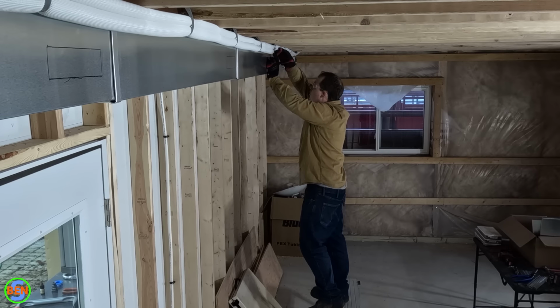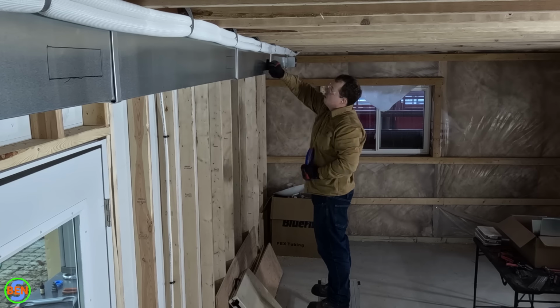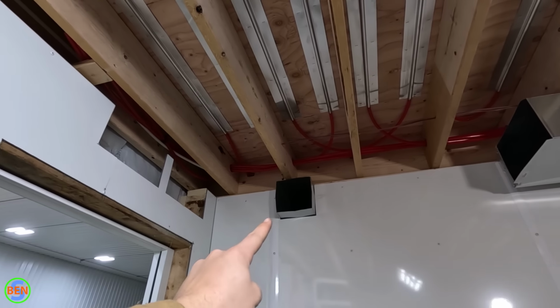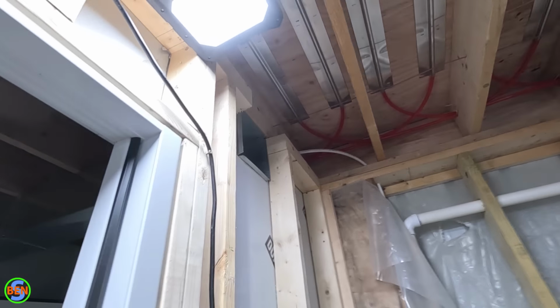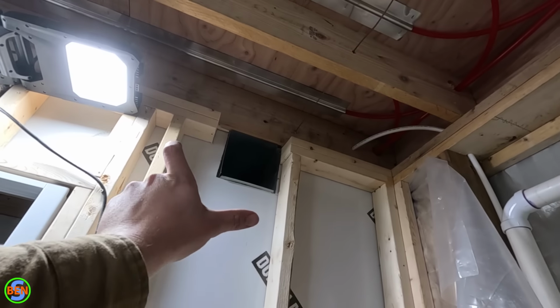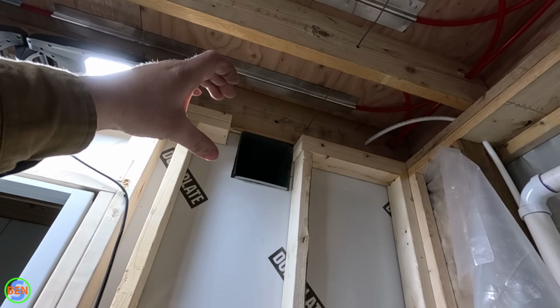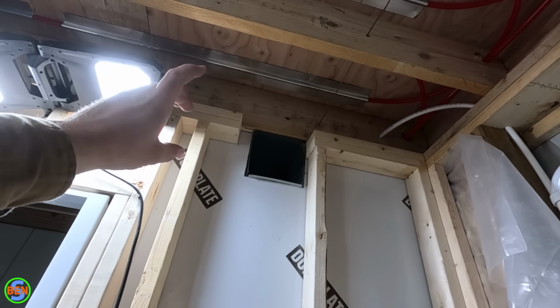So we got all that ductwork sized up and ran. We have ductwork going over to an office area, so supply ductwork and return ductwork to that area. And then we have just a supply duct going to our bathroom, because generally speaking, you don't really want to run return lines from bathrooms. Basically, that room will be slightly pressurized from that air vent, but that's a good thing.